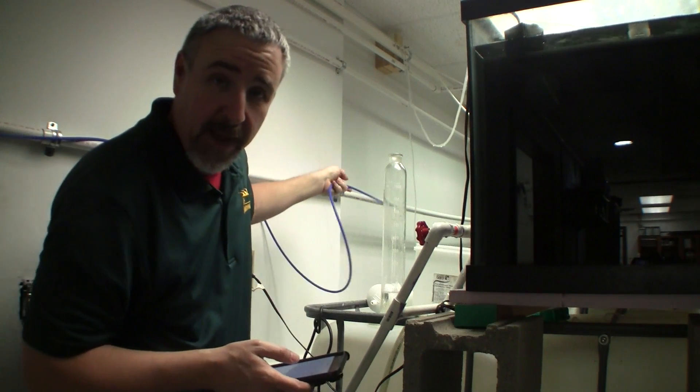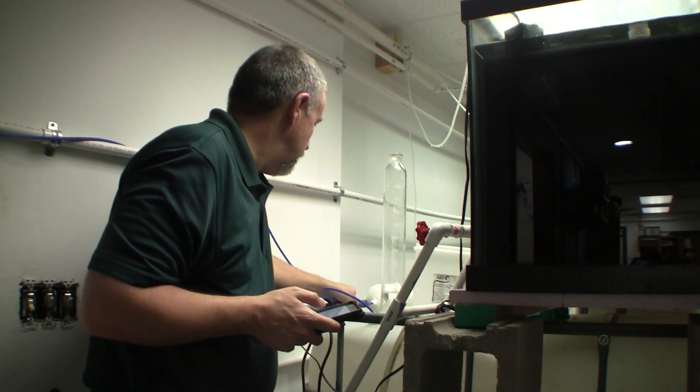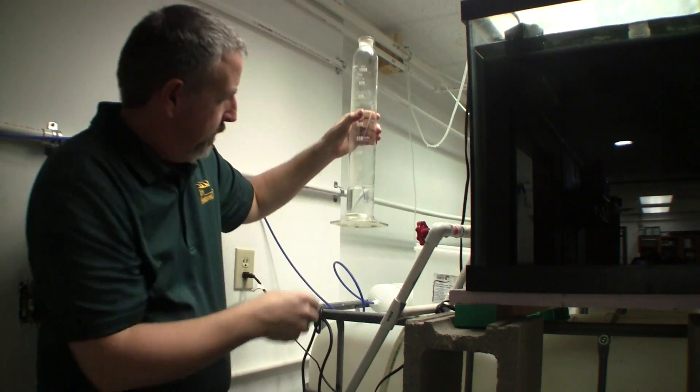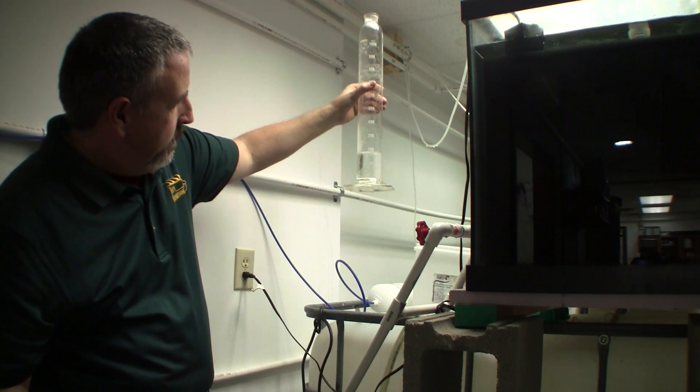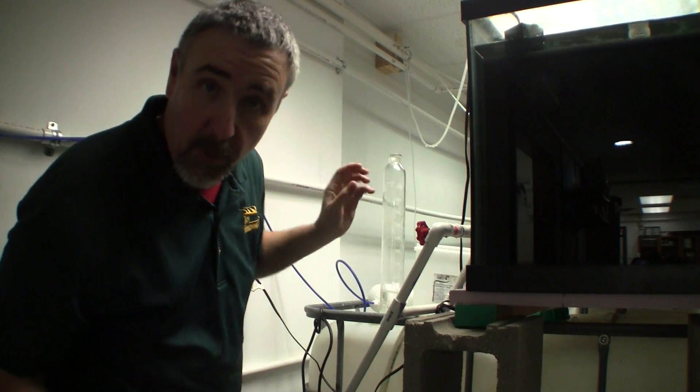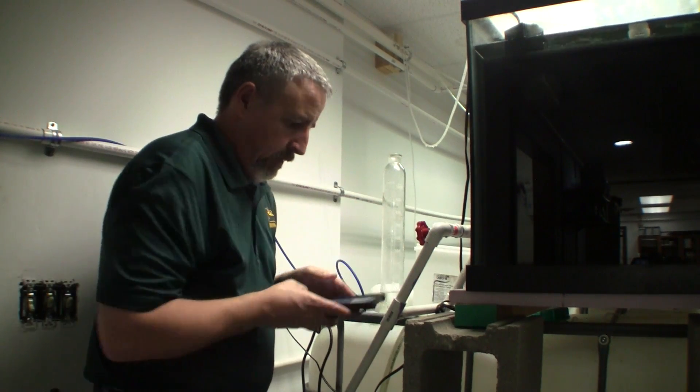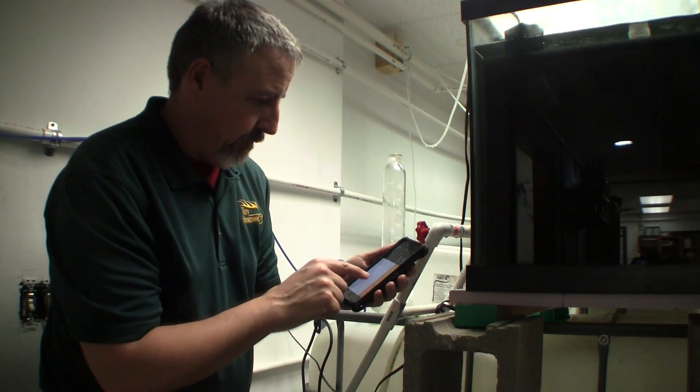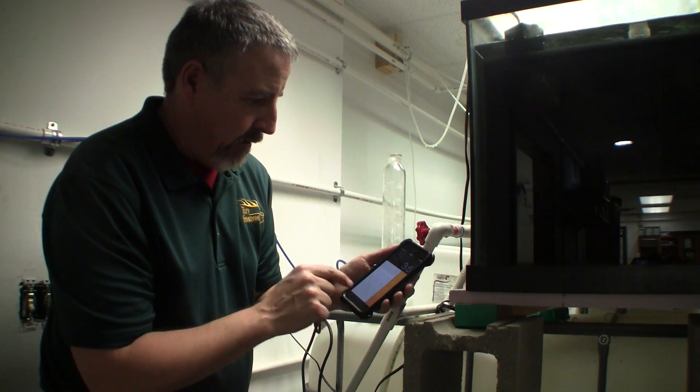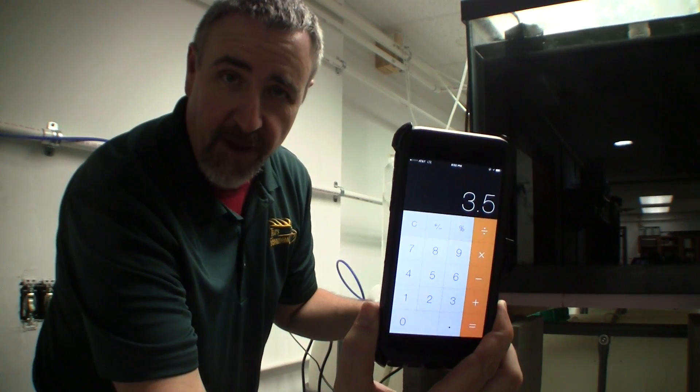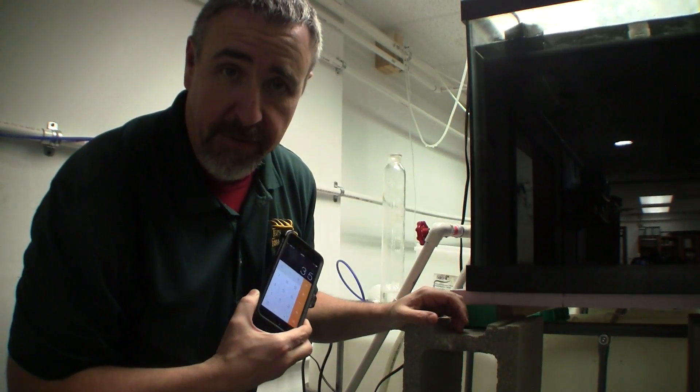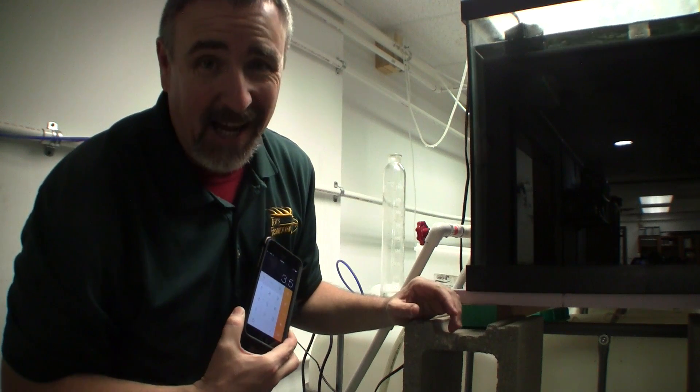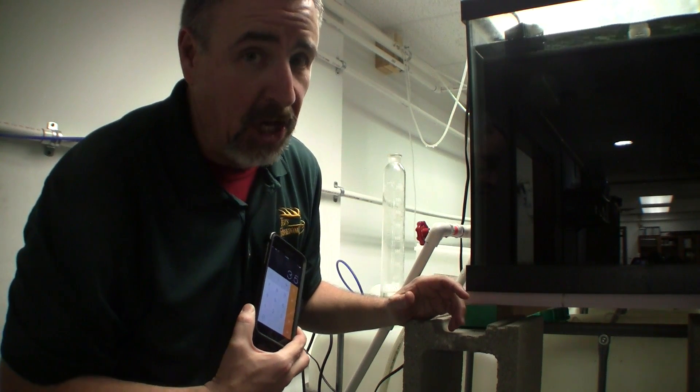Okay. Let me plug this back in so I don't keep dripping water everywhere. Now we'll take a look and we are right at 180. So I'm going to take my calculator. 630 divided by 180, 3.5. That's pretty good. I'm happy with that. I don't want to shorten my restrictor because I don't want to go any lower than 3.5. I might actually ask them to send me a longer restrictor and maybe get closer to 4.0.